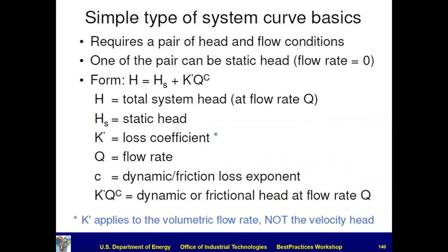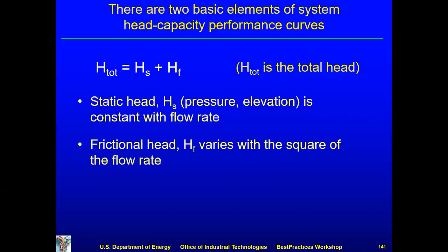I don't know why, but we have certain variables that we just use all the time. Q is flow rate, typically gallons per minute. C is just the exponent that we want to assume, usually 1.9 or 2. And then the frictional head or dynamic head is that product, K prime times Q, the flow, raised to the C power. So when you look at that, total head H is equal to static head plus the friction head. You're just going to add them together. The static head is caused by overpressures in tanks and elevation differences, so it has nothing to do with flow rate. And the frictional head has everything to do with flow rate. It basically varies with the square, almost the square, of the flow rate, whatever exponent you want to use.